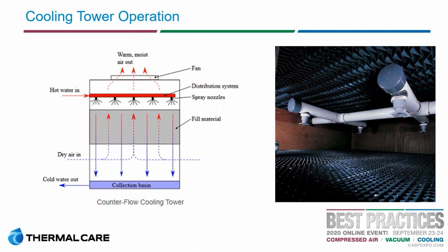And so as we drag air across that water, we get the evaporation, and that evaporation is what actually performs the cooling. The water that doesn't evaporate has had energy pulled out of it, which lowers its temperature. It then gathers in the bottom, in the collection basin, as the now cool water that we'll be using.